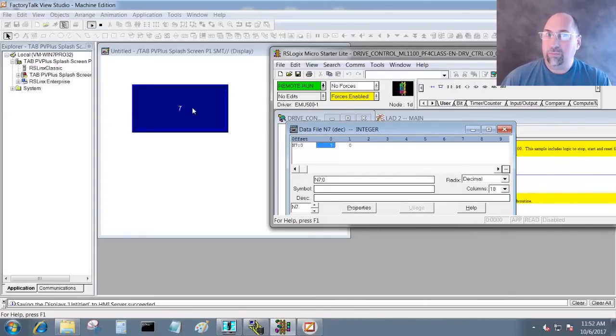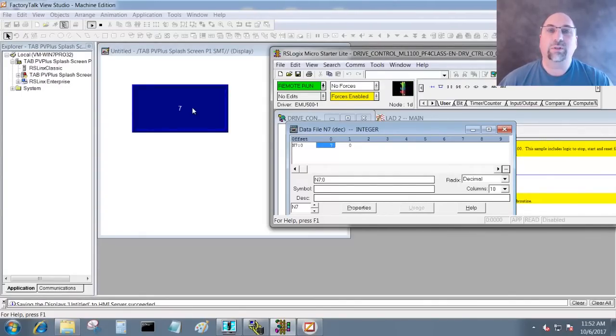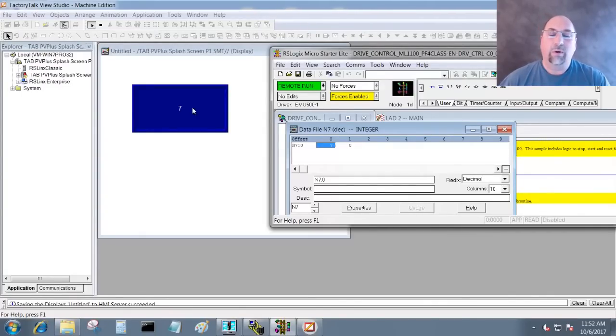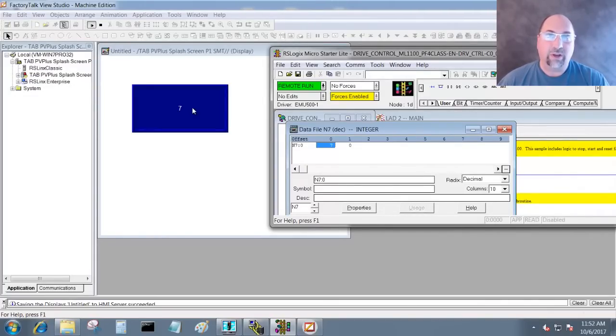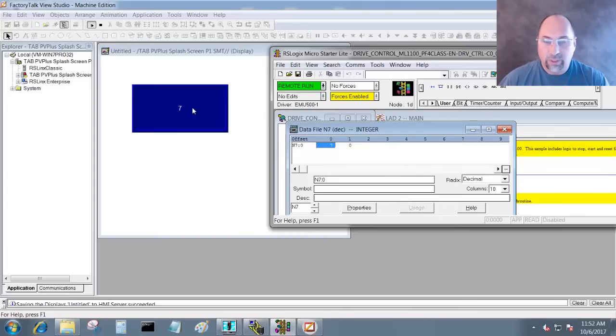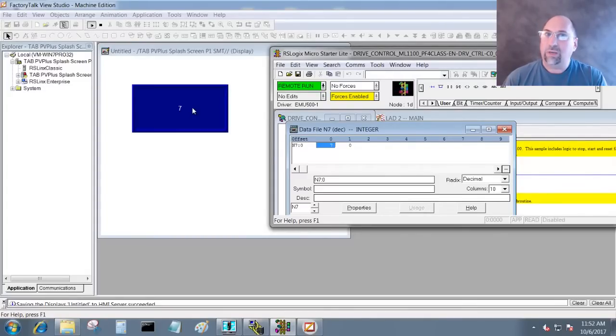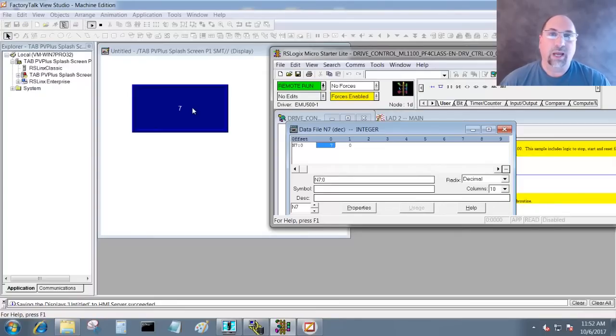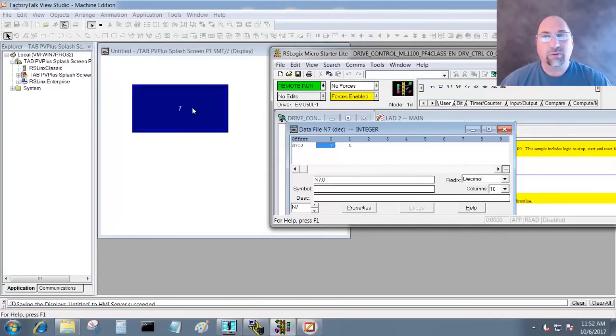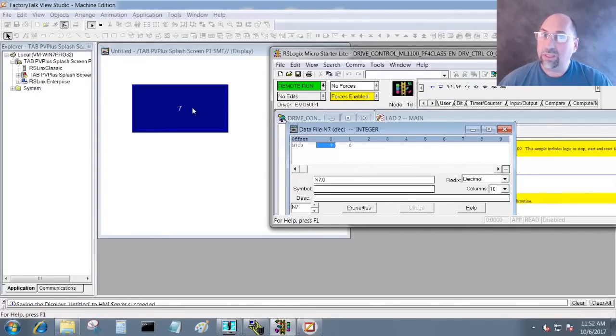Now the only thing that really could stop this from working is if you didn't have a license for FactoryTalk View. If you have a license for FactoryTalk View, even if it's a temporary license, it should activate RSLinx Classic to be able to do this. However, if you don't have a license for FactoryTalk View and you don't have a license for RSLinx, then OPC won't be enabled.